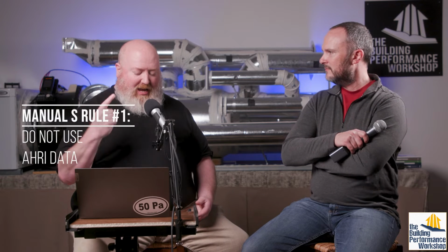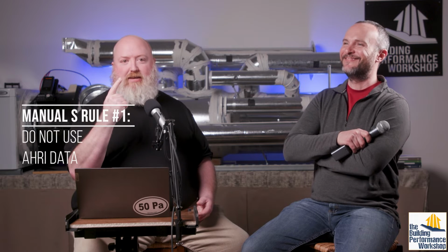Rule number one: do not use AHRI data. Literally rule number one. Did you know the AHRI capacity? I told Corbett we were going to have a coming-together moment when we talk Manual S—that contractor who looks at your load calculation and says, man, no way, there's no way, I need a bigger system than this.